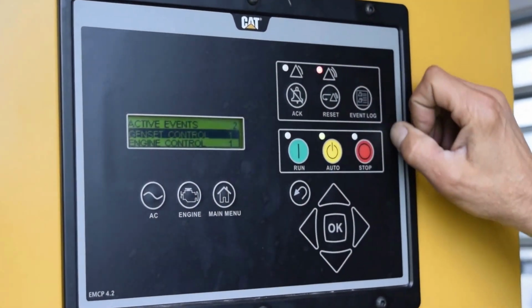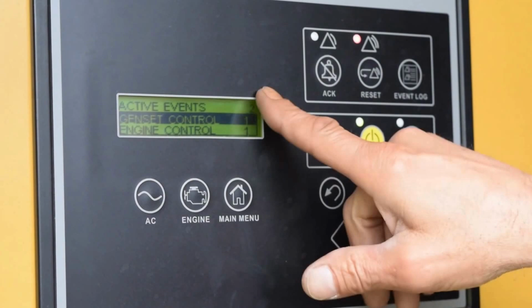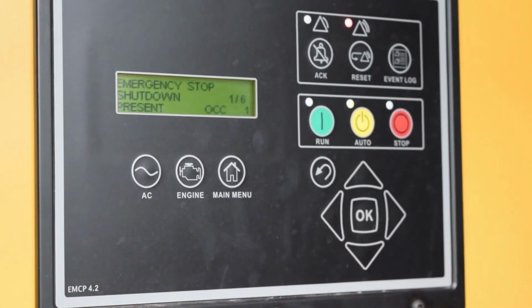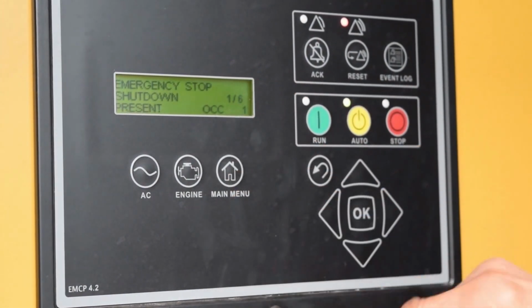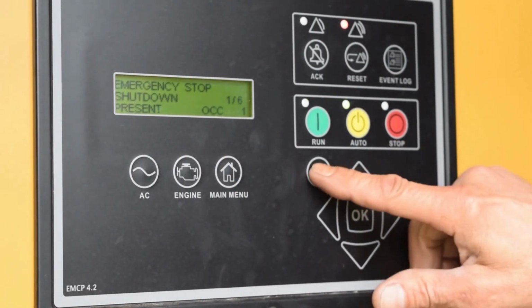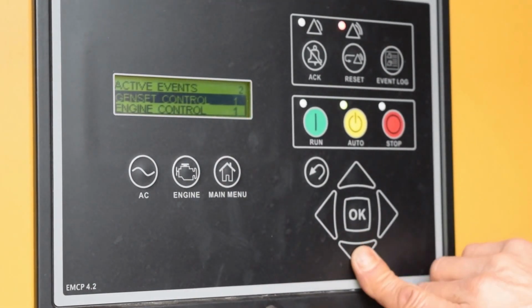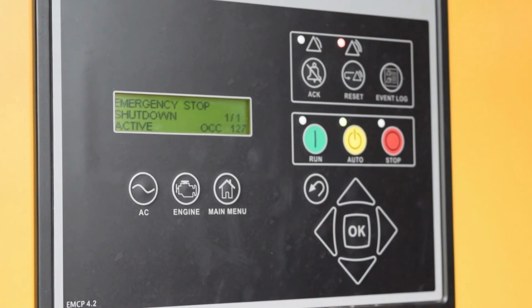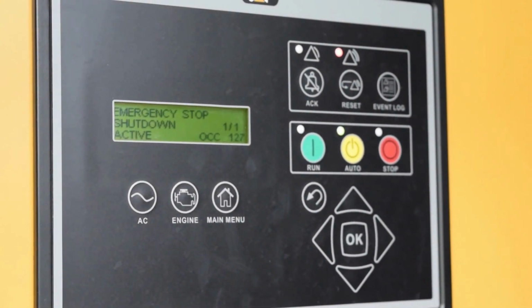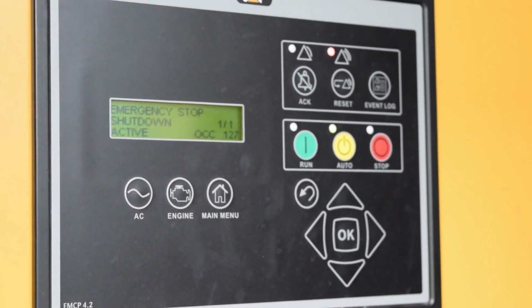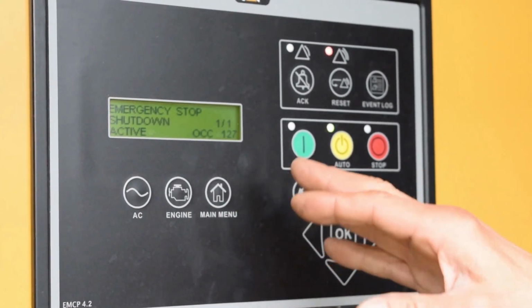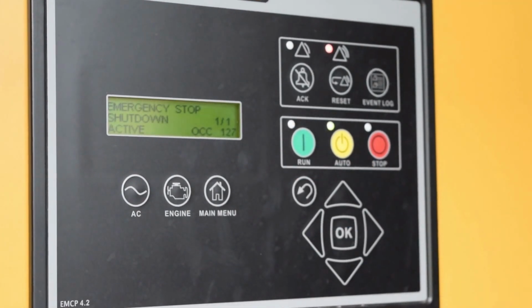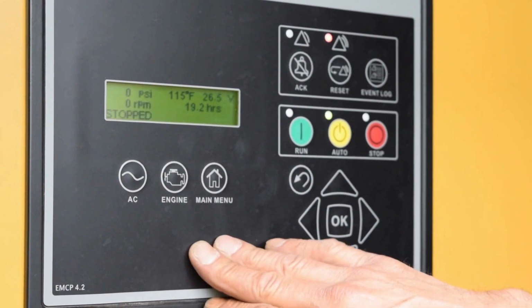we're going to go back to the beginning of event logs. We have a couple things going on now. We have two active events. One in the genset control, which is the emergency shutdown is present. And if we back out of there, we have one in the engine control, and that's going to say that emergency stop is active. It actually activates both. We actually remove power from a portion of that computer so that it cannot function.